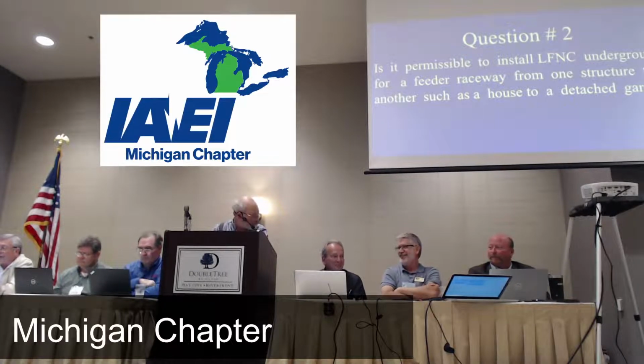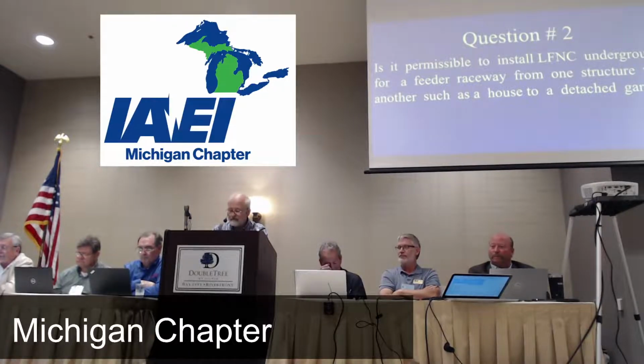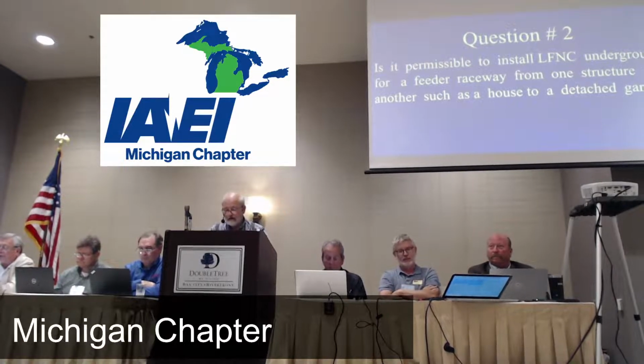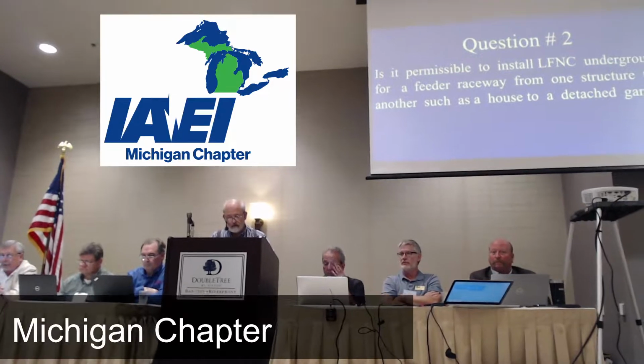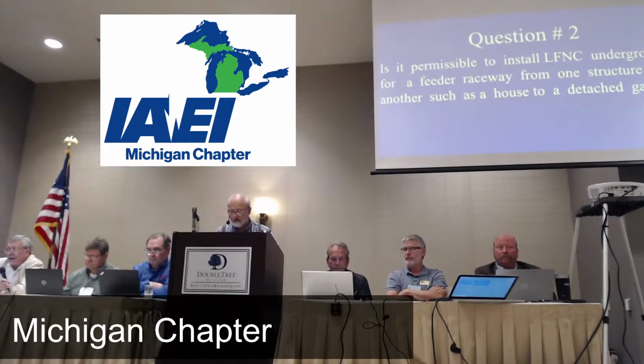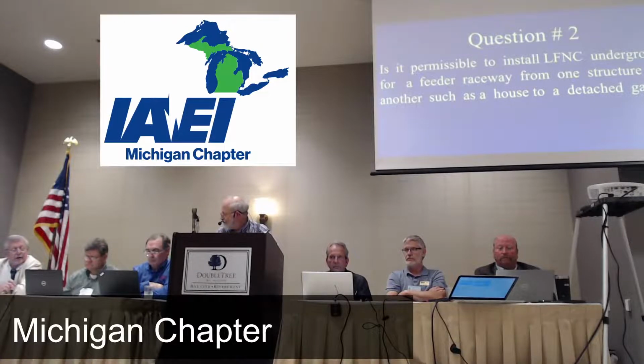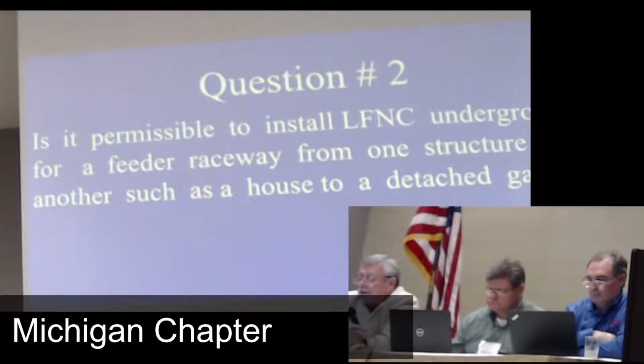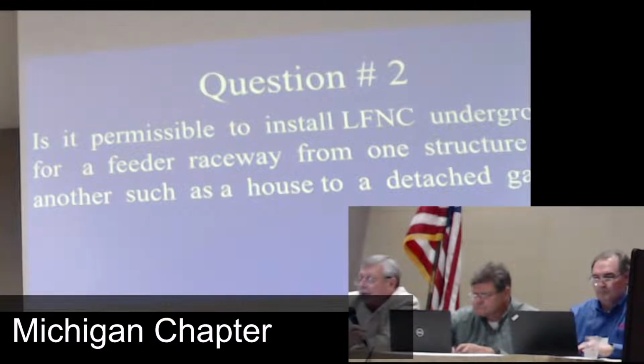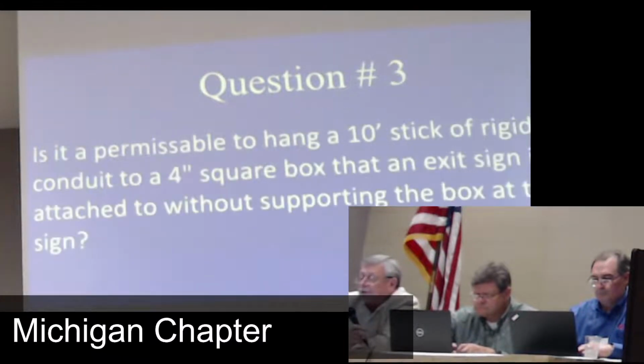314.23, and it describes the minimum support for boxes, enclosures, etc. Specifically, I go to 314.23(F), and it talks about raceway supported enclosures with devices, luminaires, or lamp holders. So I'm guessing that this exit sign is a lighted exit sign, otherwise we shouldn't be talking about electrical. And if so, it is a luminaire. So the basic rule is that an enclosure, if you're going to support it from conduit, must have a minimum of 2 conduit entries threaded into the enclosure or into threaded hubs. I'm not picturing that in this installation in any way, shape, or form. It also must be secured, the raceway would have to be secured within 18 inches of the enclosure.